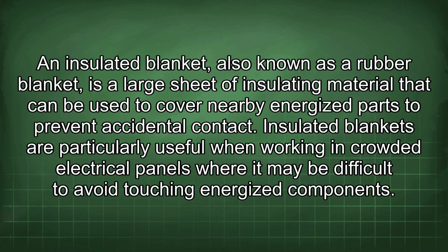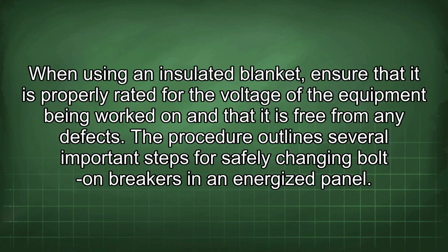An insulated blanket, also known as a rubber blanket, is a large sheet of insulating material that can be used to cover nearby energized parts to prevent accidental contact. Insulated blankets are particularly useful when working in crowded electrical panels where it may be difficult to avoid touching energized components. When using an insulated blanket, ensure that it is properly rated for the voltage of the equipment being worked on and that it is free from any defects.